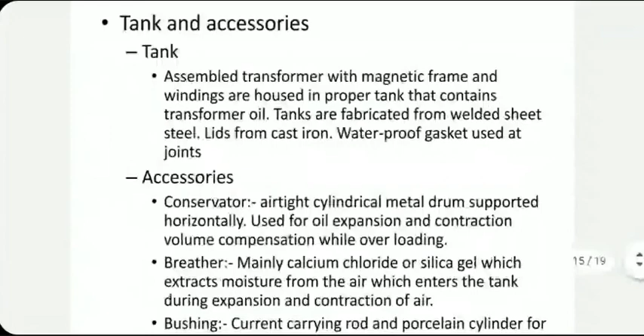There's a tank which submerges the entire assembly, and the oil is there. Oil has to be changed periodically because it gets contaminated with time. Regular maintenance requires that oil should be changed, or at least inspected for sure.